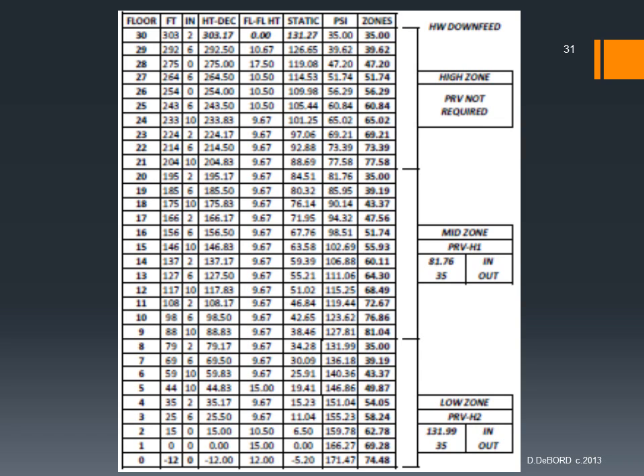So you might notice that we don't need a PRV on the top zone, but on the mid zone and low zone, we're down feeding in this case. So you see that the pressure coming in is 81.76 for the mid zone and 131.99 for the low zone, because we're pumping up with the cold water main, and then we're coming down to a downfeed system on the cold water distribution and on the hot water.